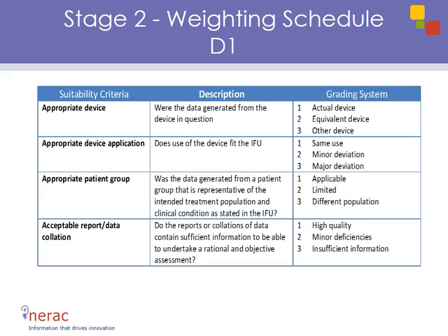It's also paramount to determine if the use of the device in the clinical study is consistent with the device's intended use and intended patient population, as described in the manufacturer's IFU. Lastly, we need to determine if there is sufficient data concerning safety and efficacy of the device mentioned in the study. Any full-text article receiving a grade of 3 for one or more of these criteria is going to be excluded and noted in the bibliography of your report.